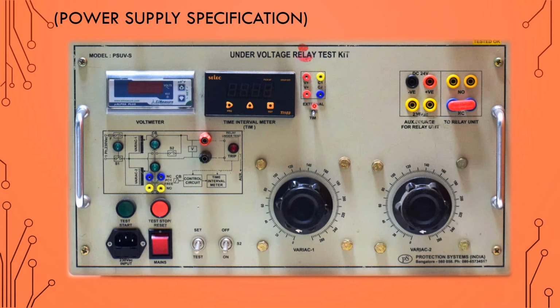And this is the power supply or the under voltage relay test unit. So this is the diagram as I showed you, and this is the test start button. That means when we press this test start button, this CB indicator will glow and it will disconnect the supply from variac 1 and connect the supply to variac 2. That means when we turn on the circuit breaker, and when we turn off the circuit breaker, variac 2 will be disconnected and variac 1 will be connected. So whatever fault voltage is applied, when we turn off, it will suddenly come to its normal operating voltage, that is 110 volt. And the normal operating voltage for the over voltage relay is less than the clock setting, but the normal operating voltage for the under voltage relay will be more than the clock setting.